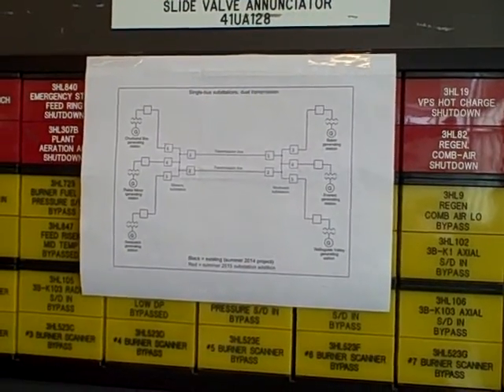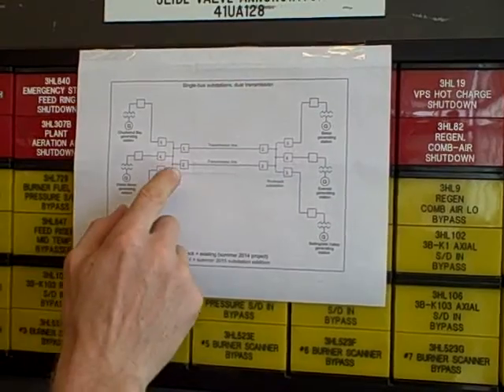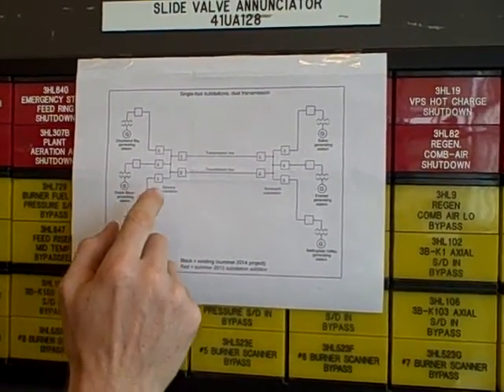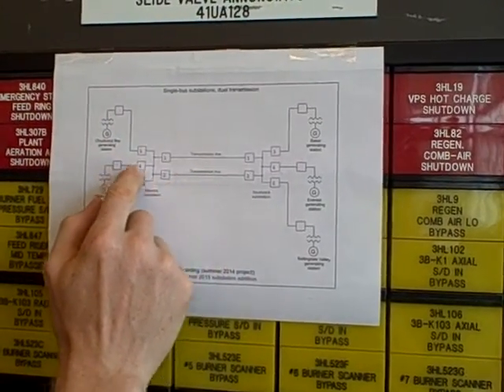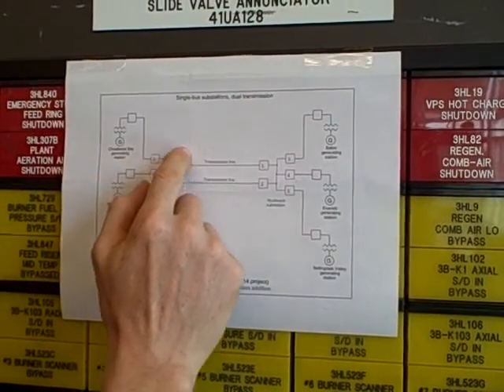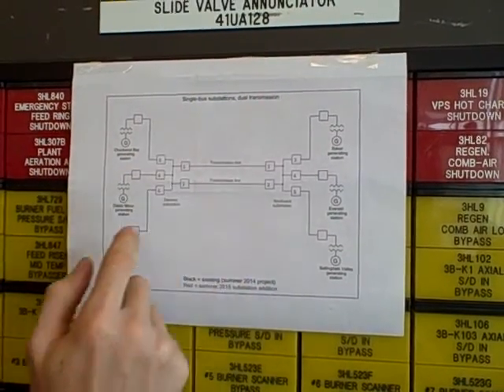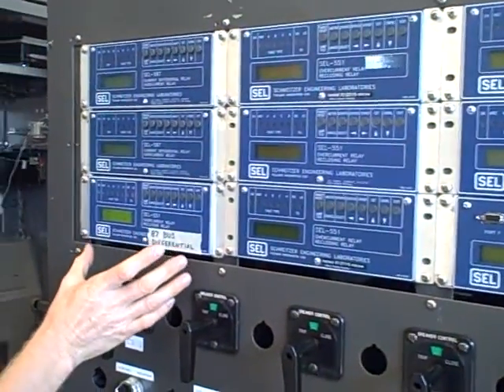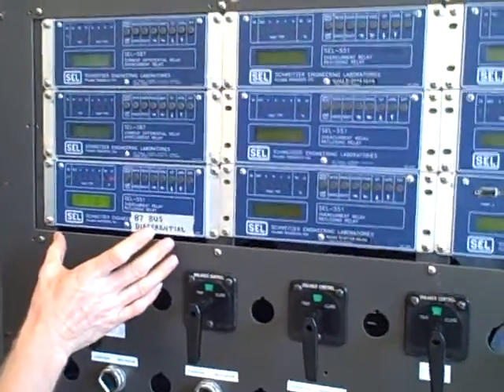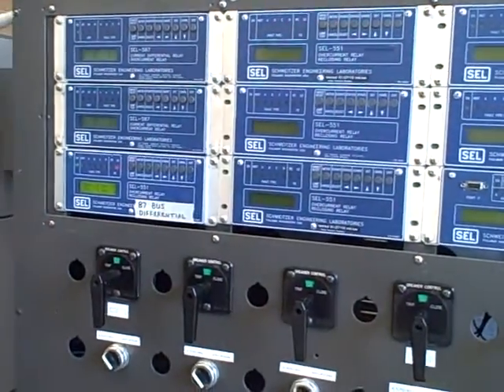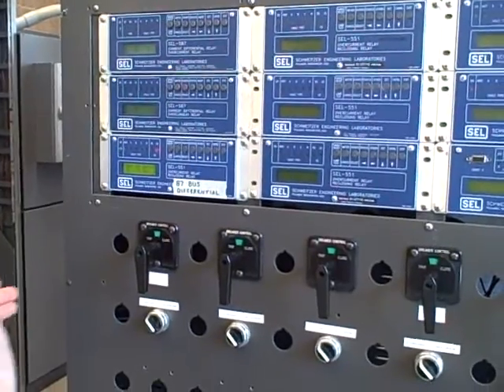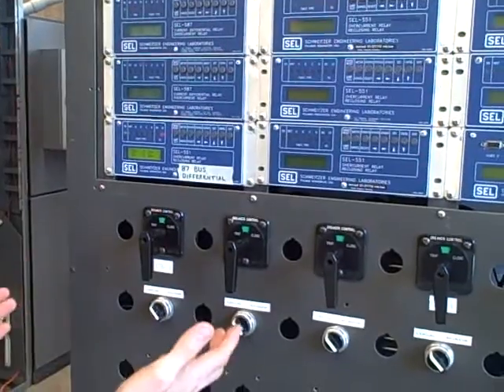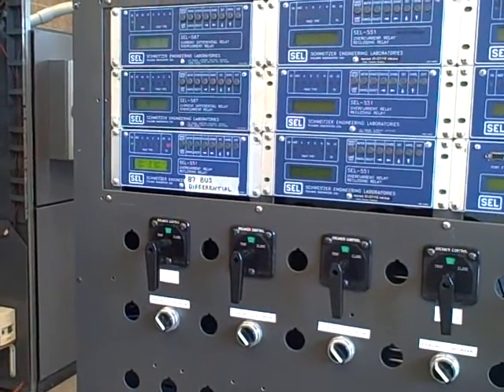So it's going to take a few seconds and then trip out. Most importantly, what I want to demonstrate is that our 87 bus differential protection will not trip, because the protection zone for 87 bus differential is simply the bus and the breakers themselves. This is a demonstration of the selectivity of this protection — it protects for faults within the substation bus but ignores faults lying outside the bus. You should never have a relay that trips outside of its zone, ideally, if the protection scheme is set up properly and everything is wired correctly.